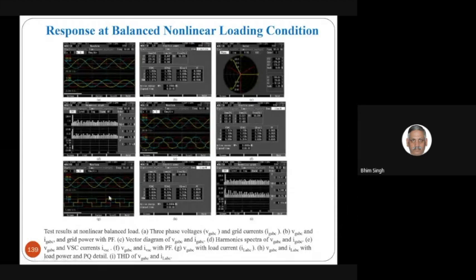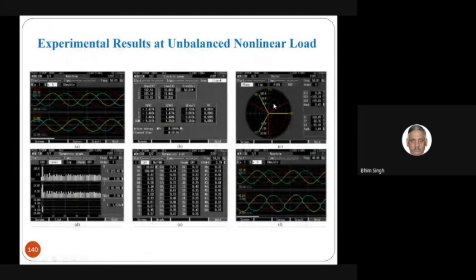However, you can clearly see the load current is square wave like, a non-linear current of a simple 3-phase rectifier or thyristor converter. These are the voltage source converter currents, which not only feed the solar power to the grid but also meet the harmonics and reactive power requirement of the load, to make the grid current balanced and result in unity power factor.